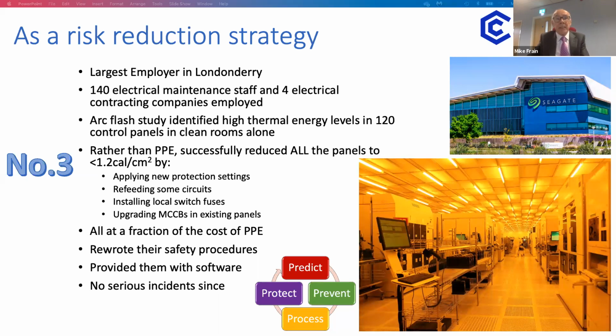We also refed some circuits, because I mentioned earlier how impedance can have an effect. So it can lower the impedance. We can increase the arcing fault, and the paradox is, of course, you increase the arcing fault in certain circumstances, that decreases the time to trip. And in that case, that's what we did in one or two instances. We installed local switch fuses on the side of the equipment. As you can see, the equipment cabinets in that picture on the right-hand side are quite numerous in that particular fab. Or we upgraded MCCBs in the existing panels.